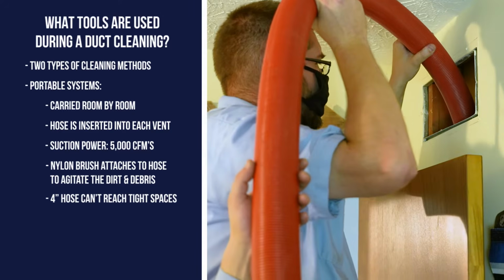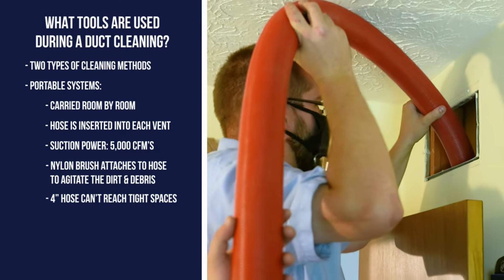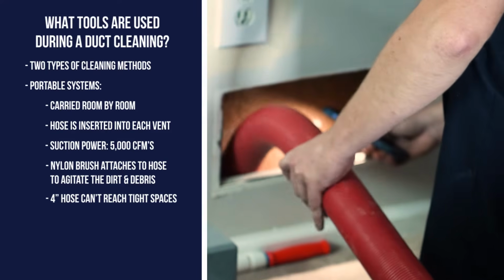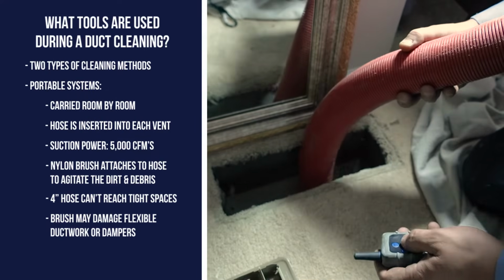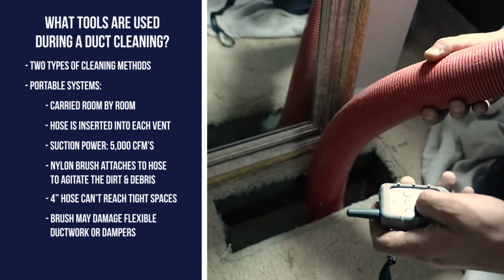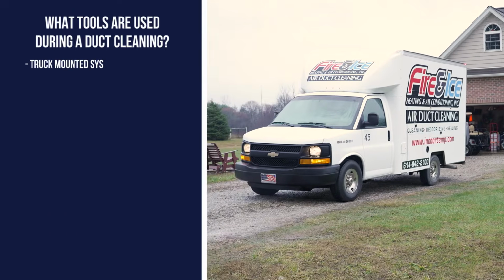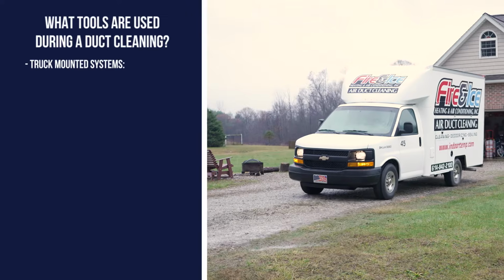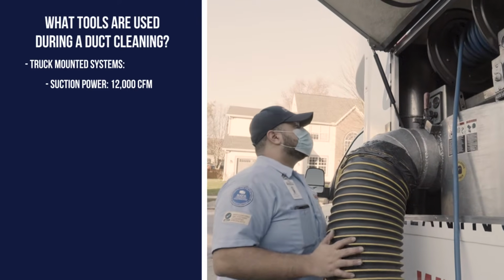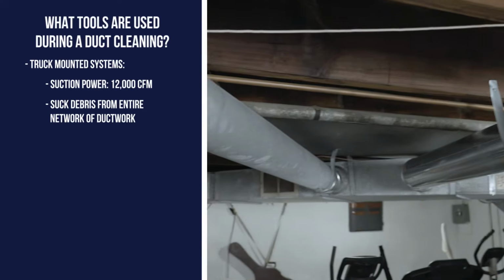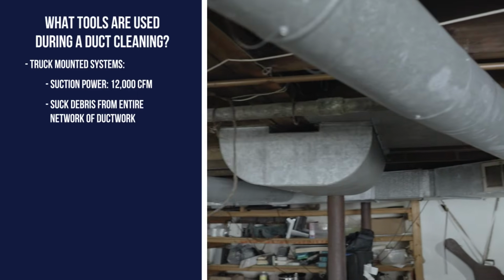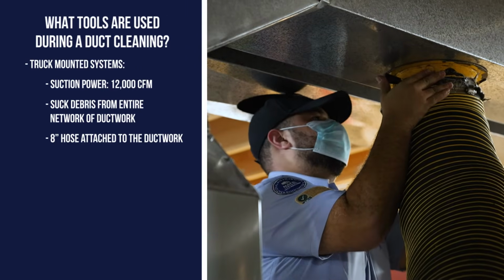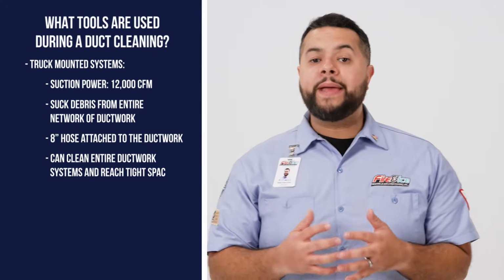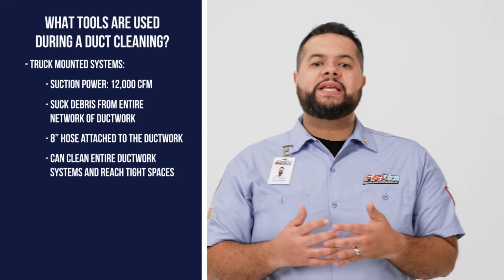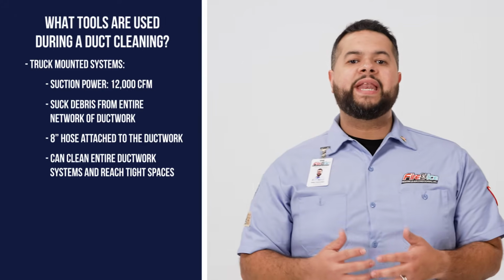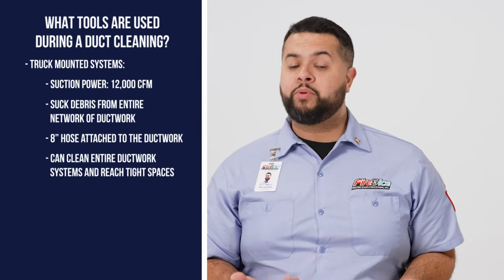The downside of this approach is the hose is about 4 inches thick and cannot get into every nook and cranny of the ductwork. The spinning brush can be aggressive too, and can damage flexible ductwork or dampers. The other option are the truck-mounted systems, which we use here at Fire and Ice. They are powerful vacuums of 12,000 cubic feet per minute. They work by sucking the debris from the entire network of the ductwork using a large 8-inch hose attached to your ductwork. The primary benefit of a truck-mounted system is it can clean the entire ductwork system and get into spaces that can't be reached by a portable system.